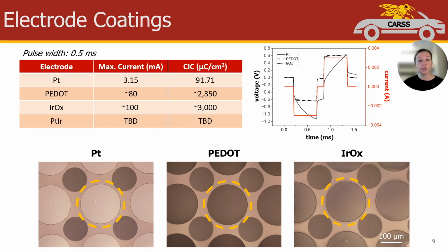We've only tested current injection of up to 30 milliamps due to limitations of our test equipment, but we anticipate maximum allowable currents of approximately 80 and 100 milliamps for these coatings based on the linear relationship between CIC and the interphase potential in the voltage transient measurement. These coatings can be seen under optical microscope, as shown in the images across the bottom. The dotted yellow line is encircling an exposed microelectrode, which appears darker in the right two images after coatings have been applied. We are also in the process of testing platinum iridium coatings, but do not yet have that data available.